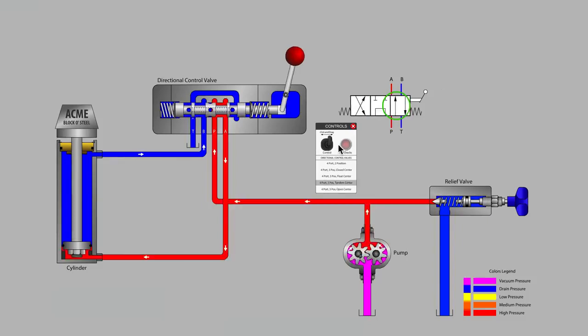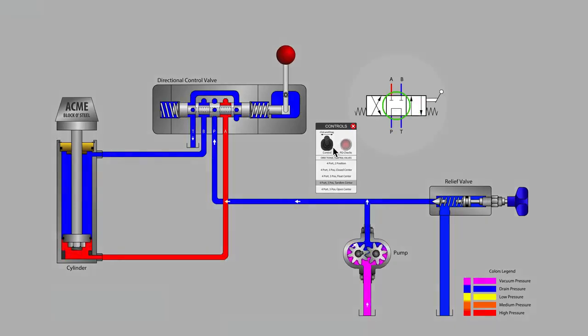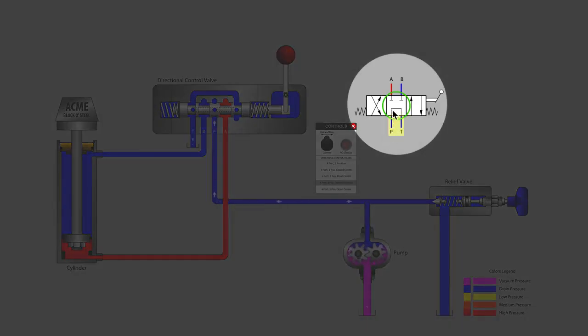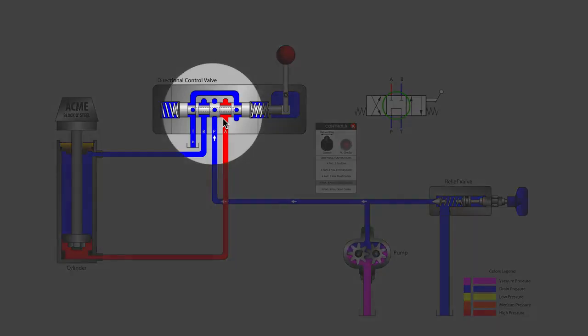Let's start with the tandem center valve. In the symbol, P is shown connected to T, while the A and B work ports are blocked. Looking at the cutaway, we see that the A and B work ports are indeed blocked in the spool undercuts and that cylinder position holding is possible. P is connected to T via a drilled and bored valve spool.